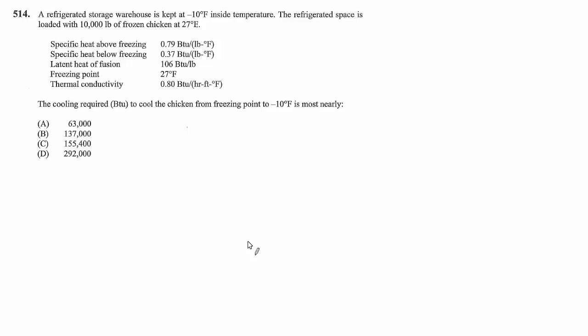So this chicken is entering at its freezing point which is 27 and it's already frozen. It says frozen chicken so it doesn't have to give up its latent heat of fusion in order to become frozen. It's already done that. All that's happening is sensible cooling from its freezing point down to the desired temperature of negative 10.